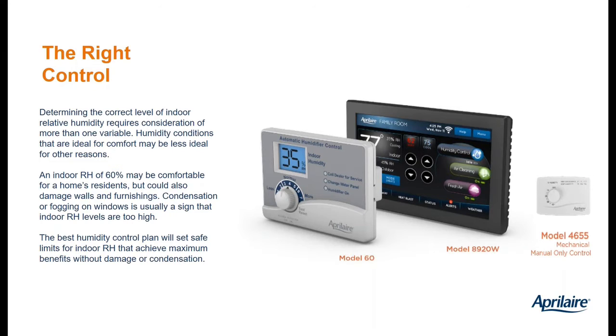That's a great option. If you think about if you have your HVAC system and your humidifier and maybe some other IAQ products controlled by a Wi-Fi IAQ thermostat, now you can view not just your HVAC system, but you can also view your IAQ products. So for a humidifier, you can see what the relative humidity in the home is. You can see if it's running. You can make adjustments to the set point if you wanted to. If you set up service reminders, you would also see that it was time to replace the water panel. You can also set up alerts through the Wi-Fi thermostat. So you would receive an email alert saying home is too humid or home is too dry. It's a great option if you have let's say a vacation home where you're controlling the heating, cooling, and IAQ in that other home or other building.